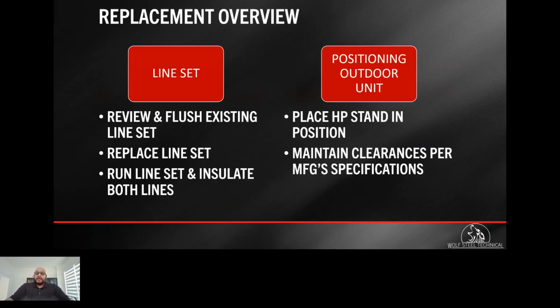If the line set has to be reused, use the appropriate flush kit. If you are replacing the lines, insulate both lines. You're going to want to place the heat pump on a stand, as the heat pump does go into defrost mode. We want the excess water to exit the unit and not freeze inside. Make sure to follow manufacturer specifications when it comes to clearances. In a home that uses propane as a secondary heat, a lot of installers forget that you do need 10 feet from a propane regulator.